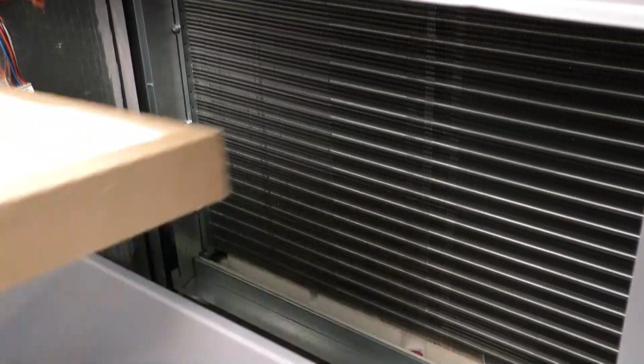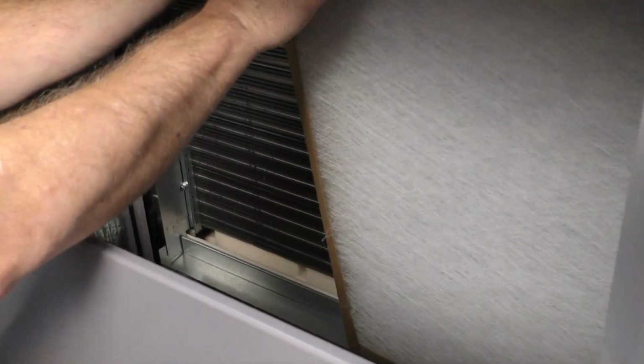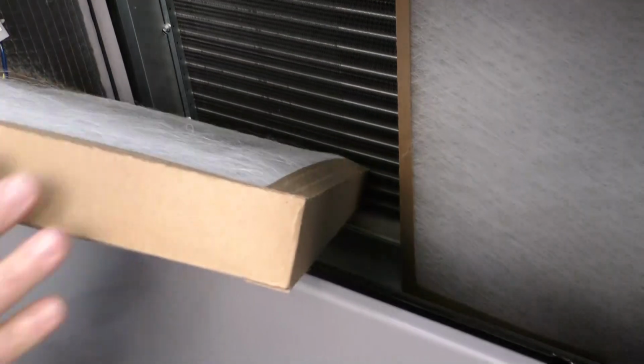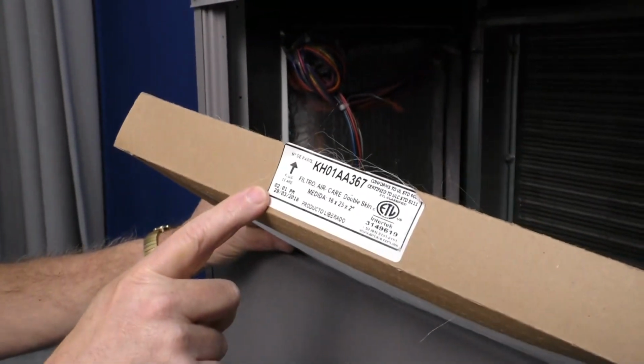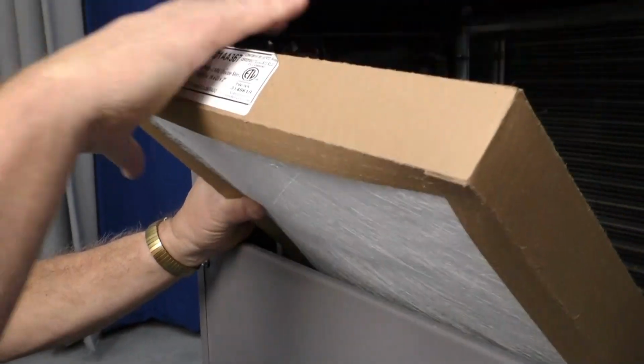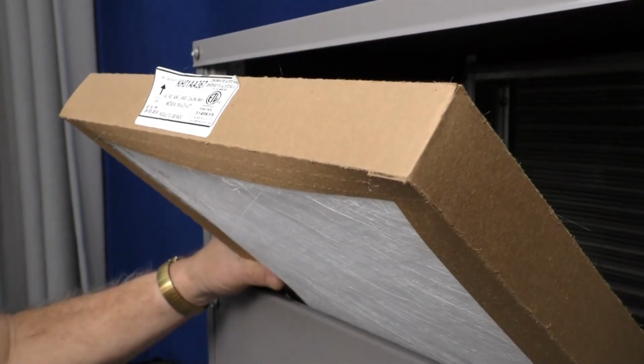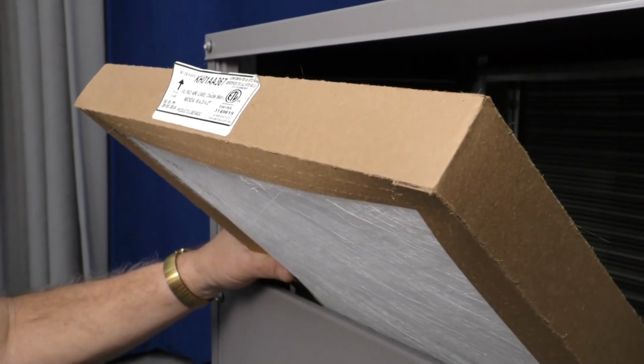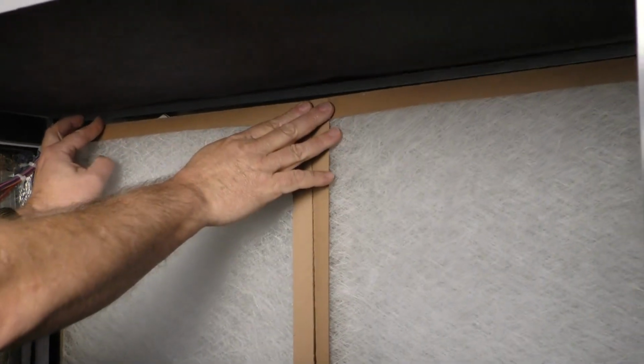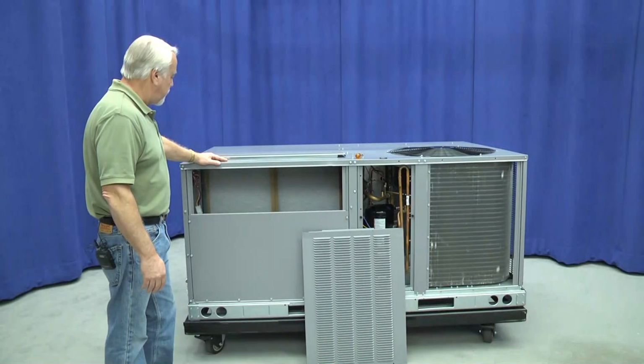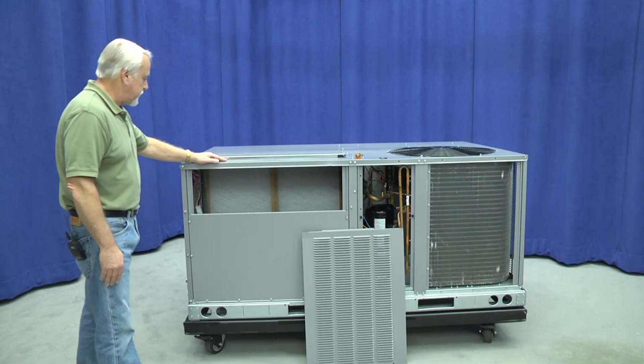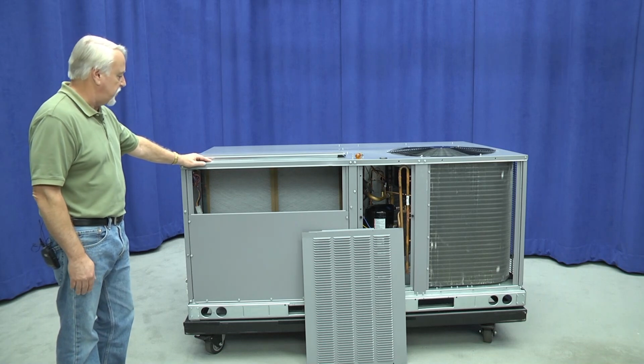The replacement of them, we align the bottom of the return air filter in the lower rail, lifting the top rail, and simply slide them into place. Pay attention, if you will, to the directional arrow on the filter, as there is a coating on the entering air side and the leaving air side that allows it to trap dust and prevent the fiberglass fibers, in this particular case, from being entrained onto the coil and into the space. Make sure that you pivot the upper rail down, which holds the filters in place. If your unit's installed with a condensate overflow switch, it'll be visible down in the condensate pan with the return air filters removed.